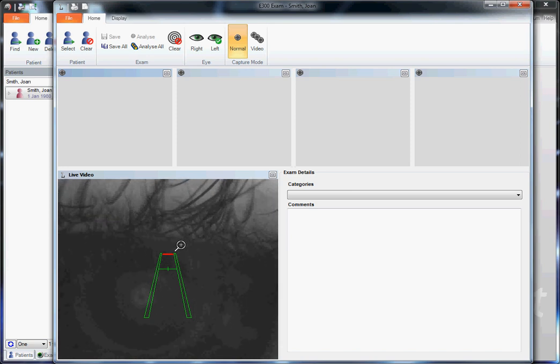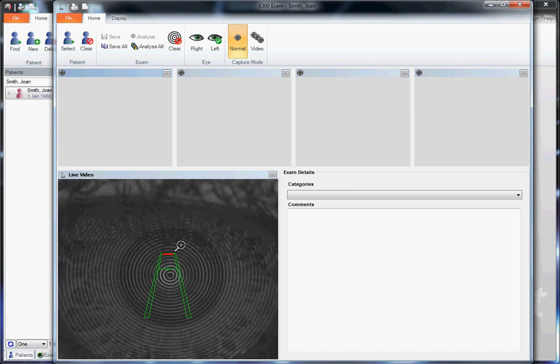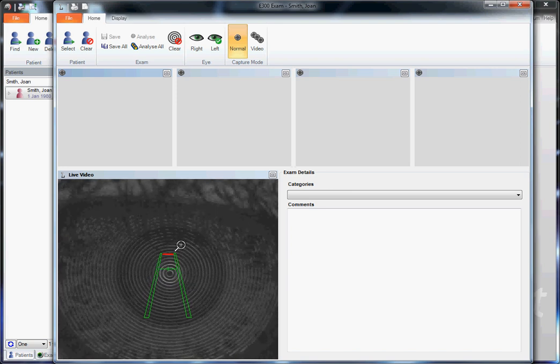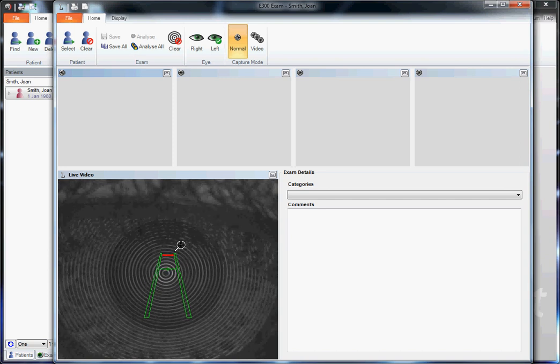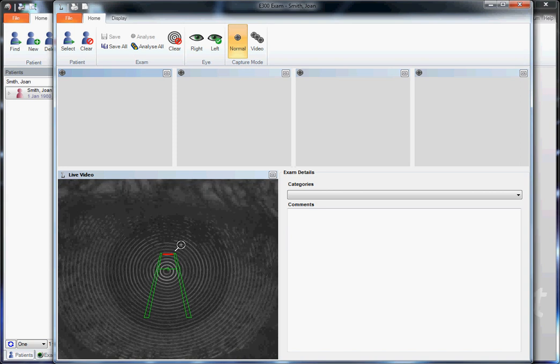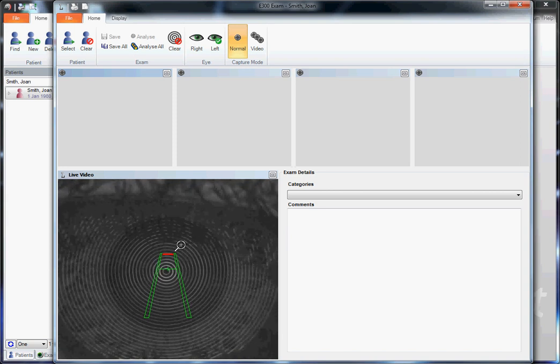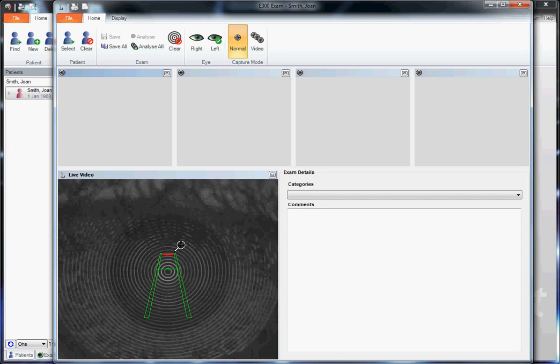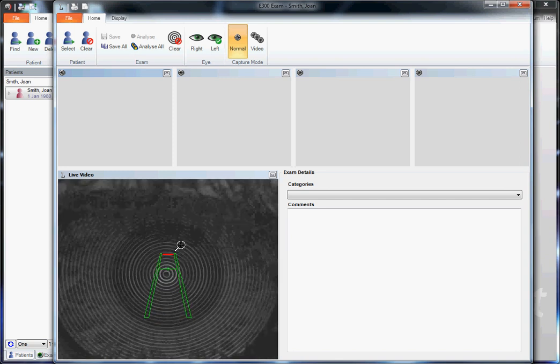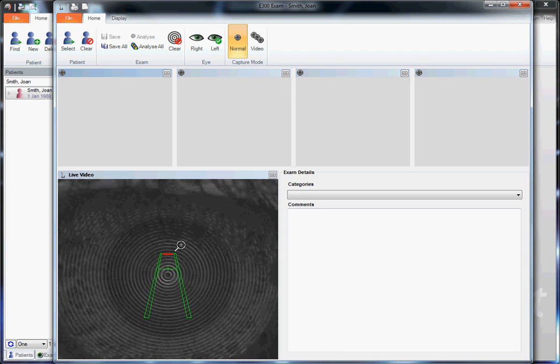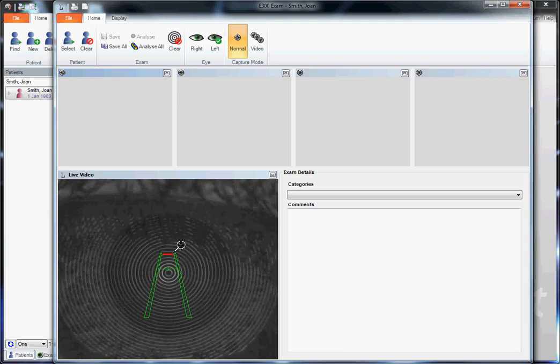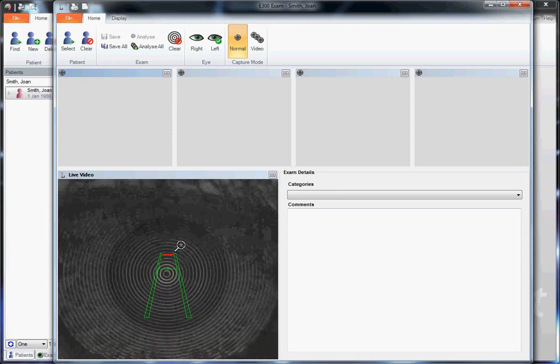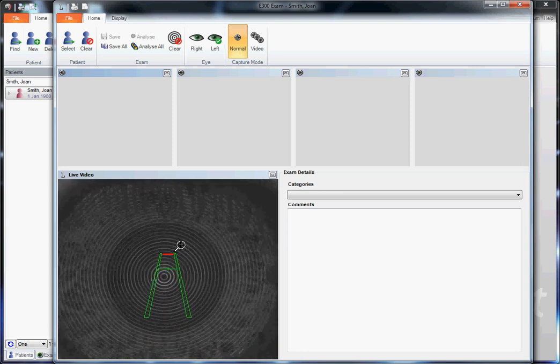When you center the instrument, look at the reflection of the Placido rings. Remember that the Placido-based topographer reflects the rings off the cornea, but that reflection is coming off the tear film rather than actually hitting the cornea. So if the tear film is poor, the underlying understanding of eye shape is similarly going to be inaccurate. It's very important that we see quality Placido reflection, with the rings looking parallel and even as they do right now.